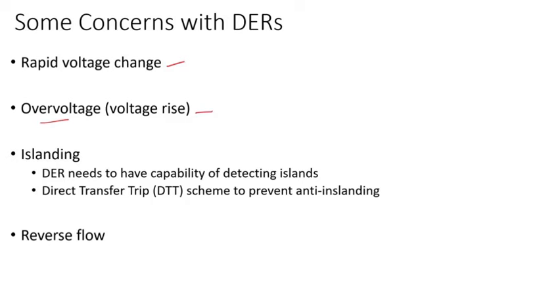You can employ a Direct Transfer Trip (DTT) scheme to prevent anti-islanding. There is also a concern with reverse flow. Again, I'll talk about these in more detail later — these are just some concerns with DERs.